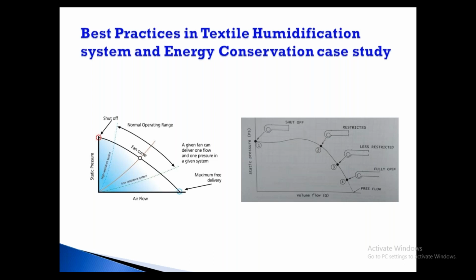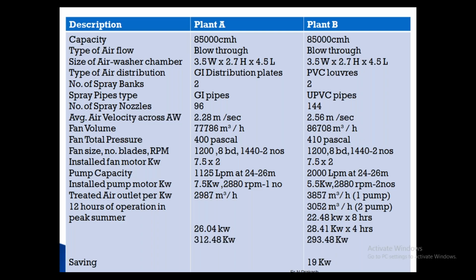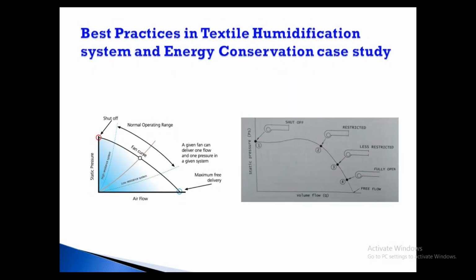As I told, there will be turbulence in the air. So the average we have to take. In some places there will be more velocity, some places less velocity. We have to take the maximum number of readings. On an average, you can find out what the velocity of the air is. Multiplied by the area, you will get the volume.